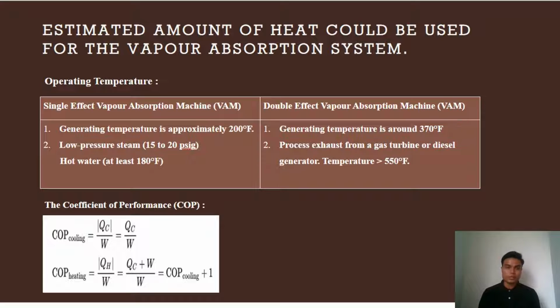Next, for operating temperature, in a vapor absorption machine with a single effect, the optimal generating temperature is approximately 200 Fahrenheit. And for low pressure steam, 15 to 20 psig is the most prevalent source of heat. For hot water, at least 180 Fahrenheit may also be utilized. In a double effect vapor absorption machine, the needed temperature at the generator is around 370 Fahrenheit. Hence, when employing the process exhaust from a gas turbine or diesel generator, the temperature should normally be greater than 550 Fahrenheit.